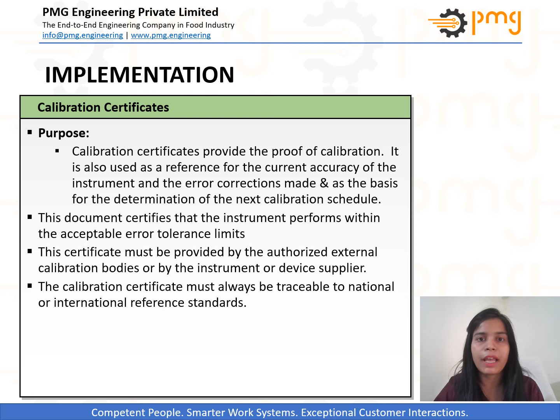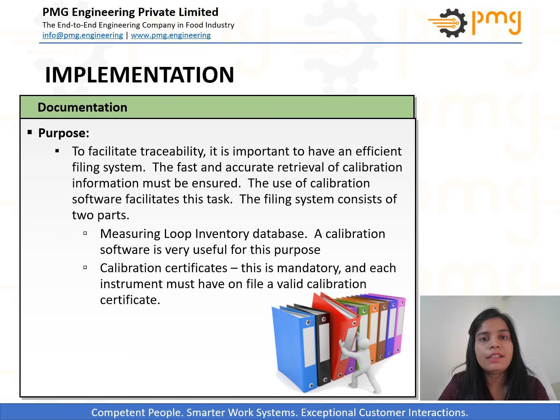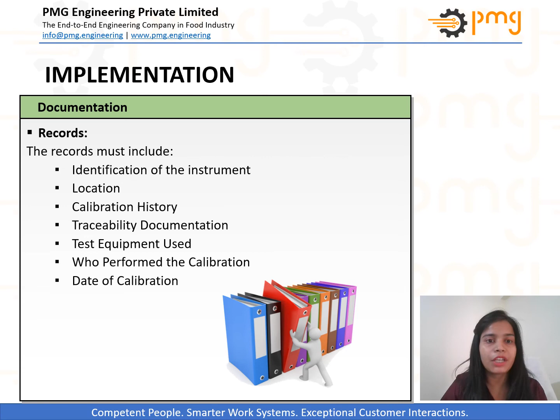Documentation. An inventory database of all field instruments and all test and reference instruments must be put in place. The database contains the following information for each measuring loop: tag number, description of instrument, location, operating range or value, maximum permissible error in measurement, instrument brand or model, calibration class, calibration interval, process medium, calibration schedule, and maintenance history of the measuring loop instrument. The records must be retained for the years specified in the record retention policy of the factory concerned. The record must include identification of the instrument, location, calibration history, test equipment used, etc.